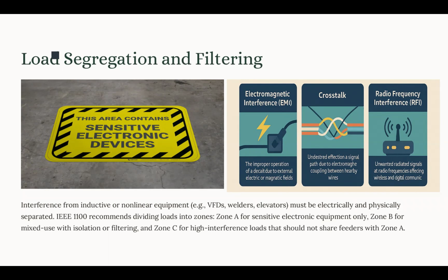We have a K-rated transformer, K13 and higher, and we have properly coordinated surge protection. The wiring in those zones should be twisted pair or shielded conductors, so we minimize the EMI in our system.